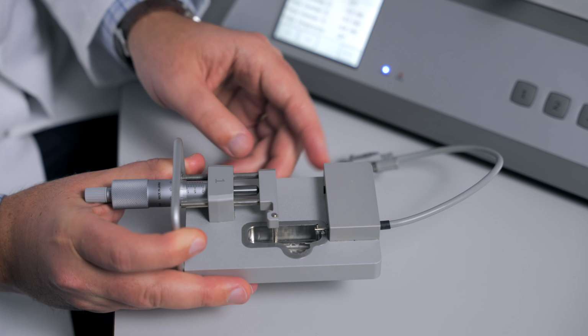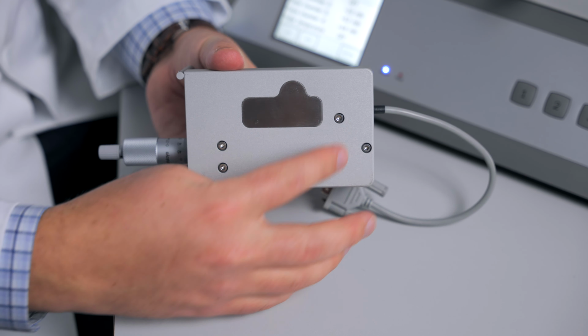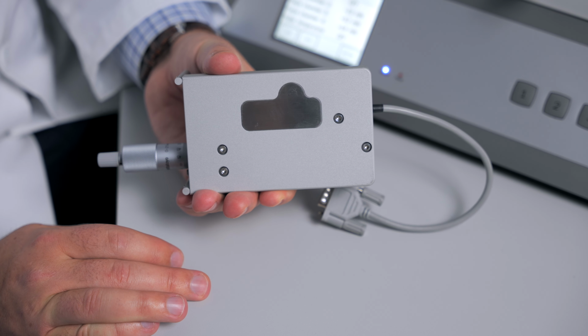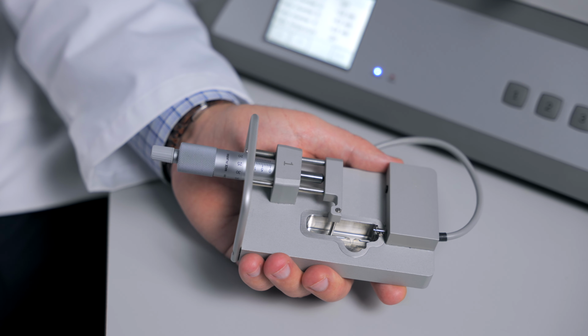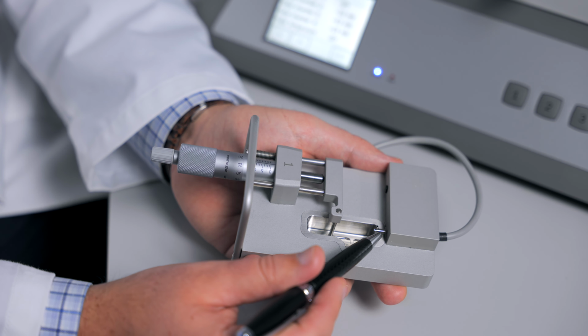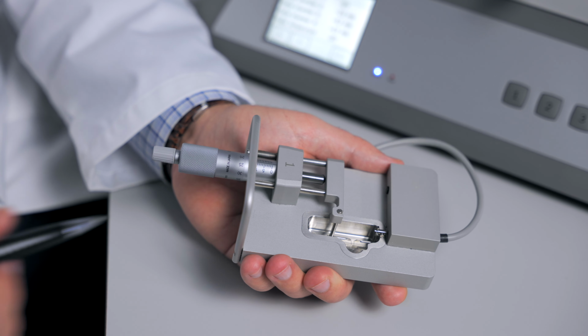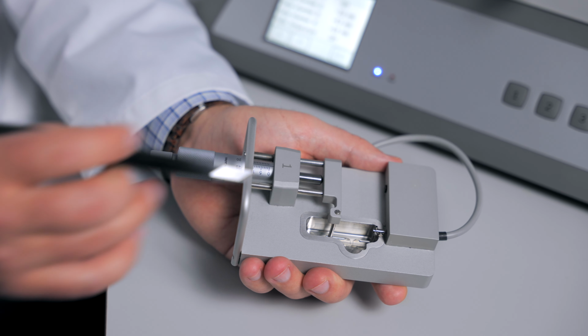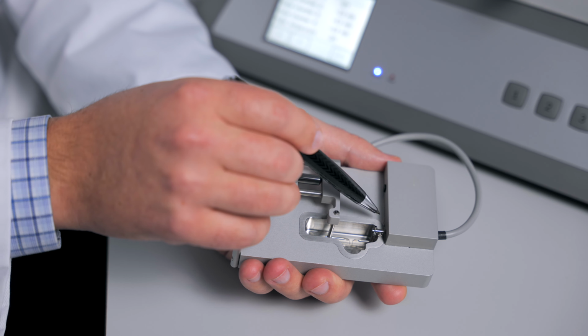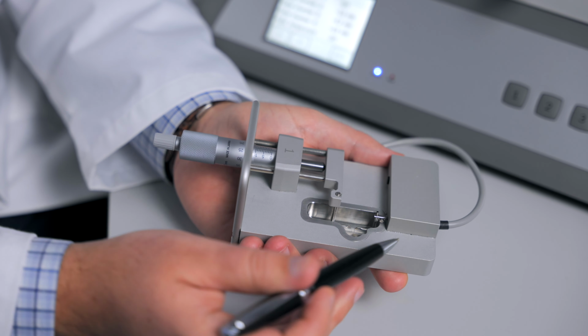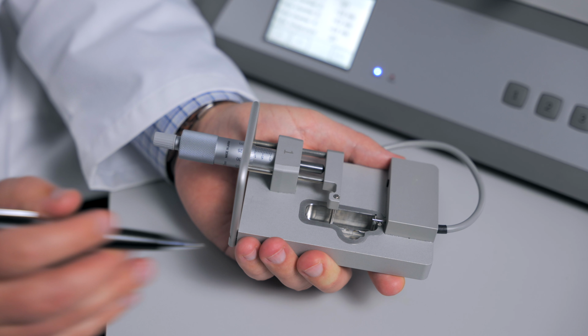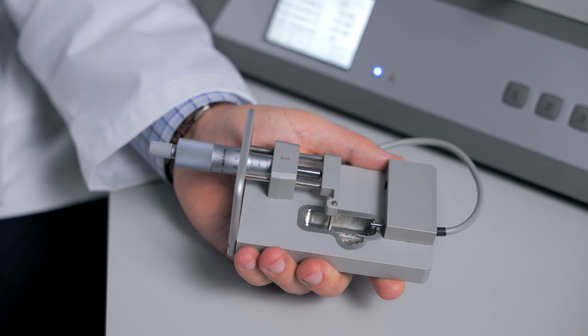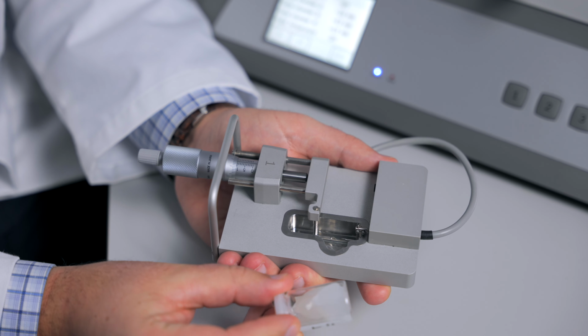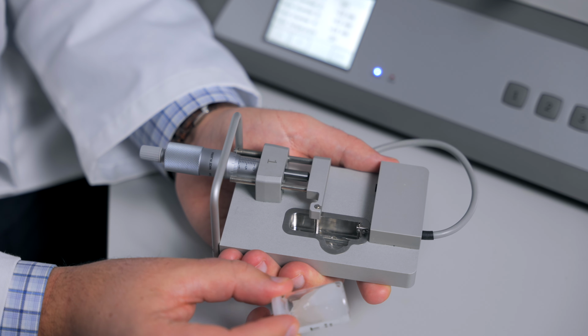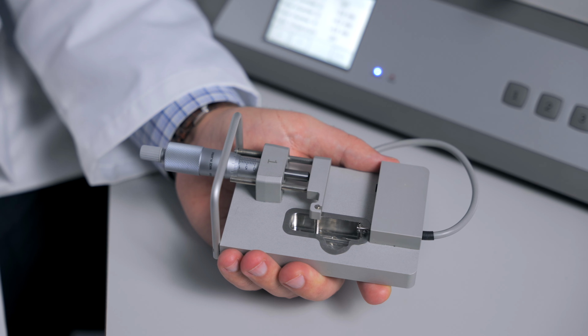Replacement procedures for the force transducer can also be found in the cleaning and maintenance section of the user guide. After your cleaning, make sure that there is still clear grease surrounding the arm that comes out of the transducer housing. You can also protect the transducer from any liquid by adding grease where the transducer housing meets the chamber. Any liquid that enters the transducer can severely damage this piece of equipment. Make sure to use the clear grease when adding any grease around the transducer.